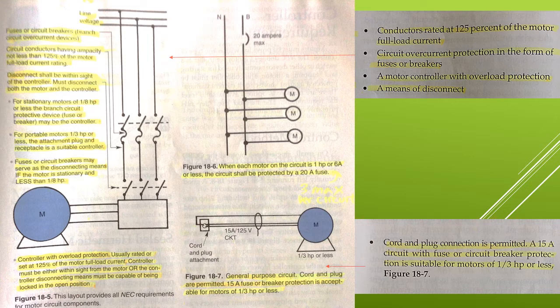Second, large motors require a controller and overcurrent protection that is approved for group installation. Third, cord and plug connection is permitted. A 15 amp circuit with fuse or circuit breaker protection is suitable for motors 1/3 horsepower or less. For this, see figure 18-7, middle bottom of the screen.